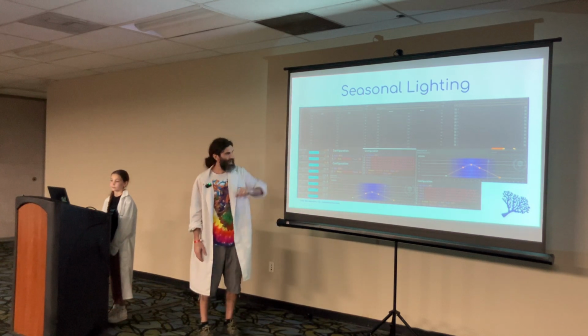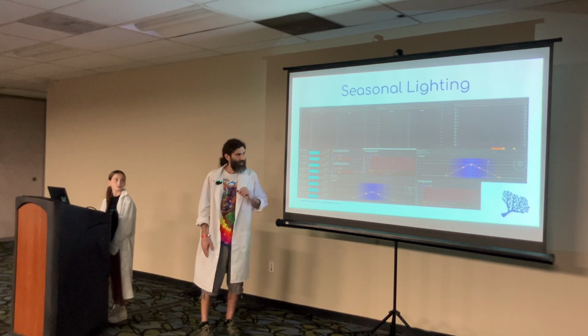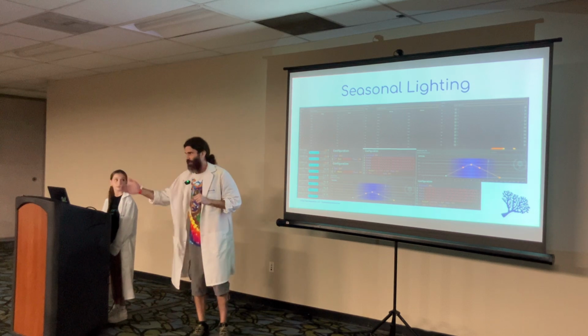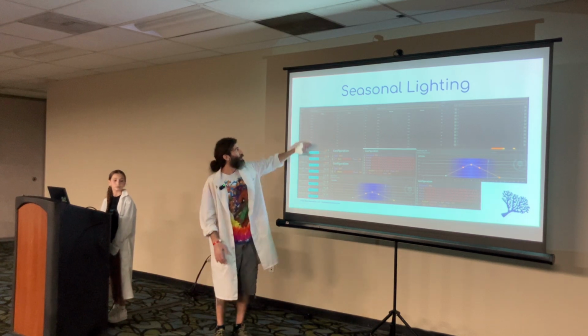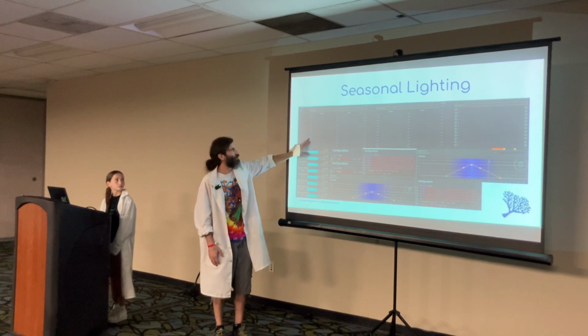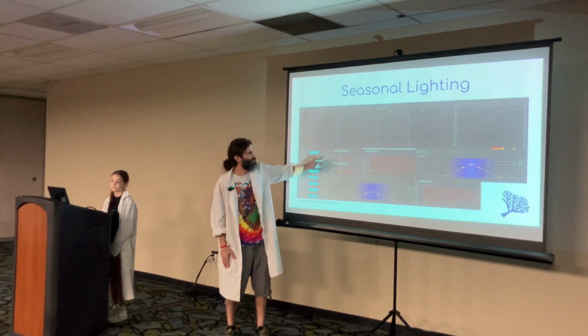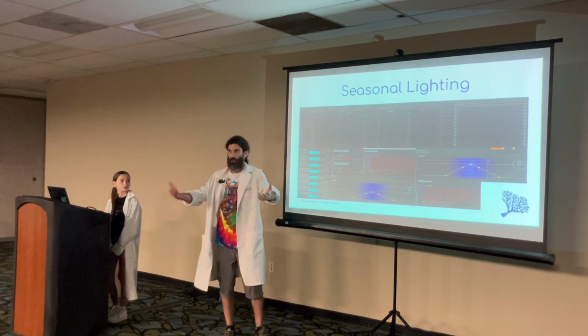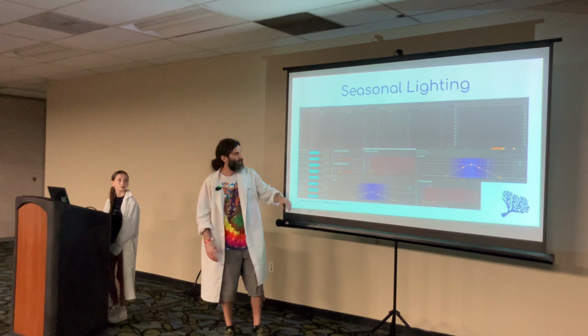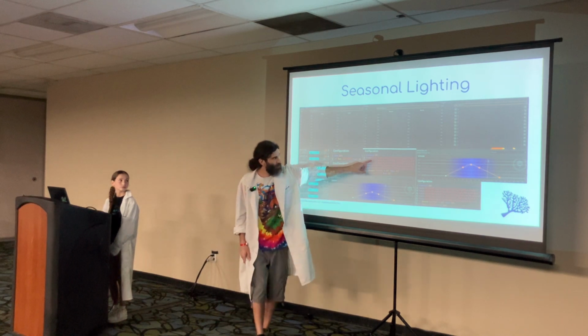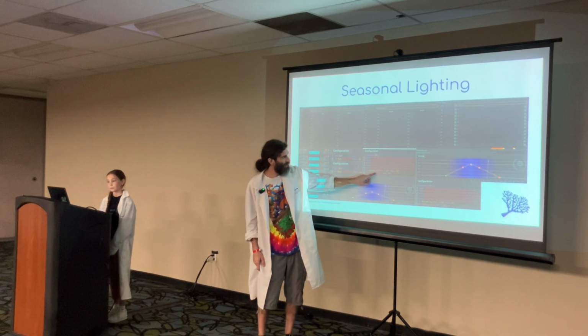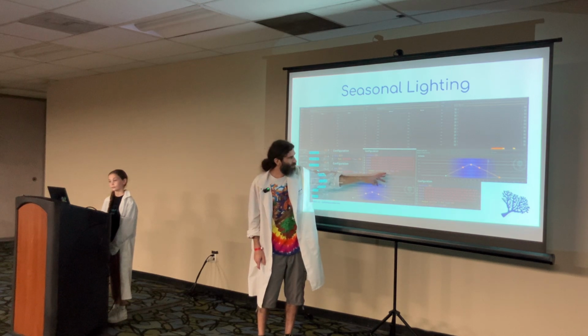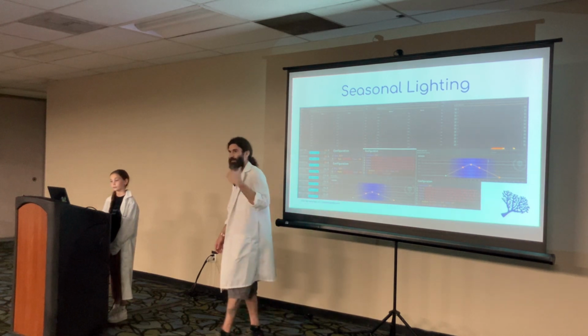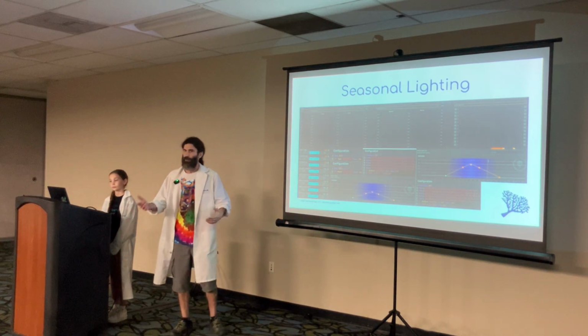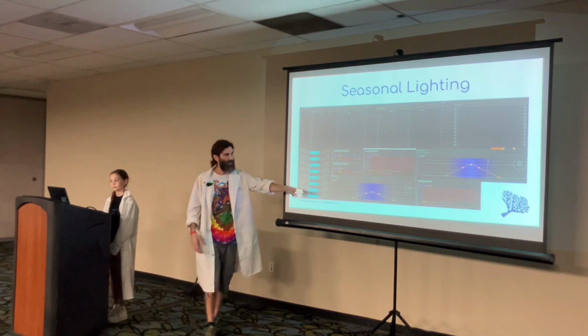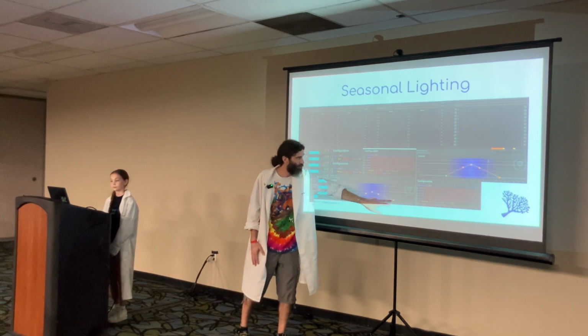If the daylight light is on, here's how I'm actually changing my seasonal times of when the schedule starts—I put in the parameters of when sunrise and sunset happen, and that's what the 'if sun' logic works on. If the sun's supposed to be on now, it's on. At the bottom of my table, if output daylight is off, then off—so if daylight's off, the lights should be off. That's how we turn them on and off, following the actual table schedule accordingly.